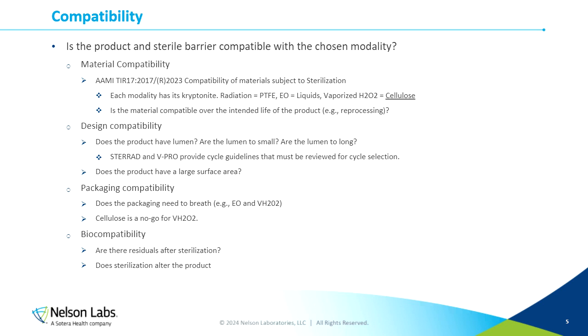And then your packaging compatibility. This takes a couple of different forms. One is, what is the nature of the packaging that you need to do? If you're doing vaporized hydrogen peroxide or gaseous sterilization, that packaging needs to be breathable. The product needs to be able to be exposed, so the gas, hydrogen peroxide or ethylene oxide, needs to be able to enter into that packaging. And that also means it needs to be able to exit that packaging as well. So the packaging needs to be considered, as well as the configuration.